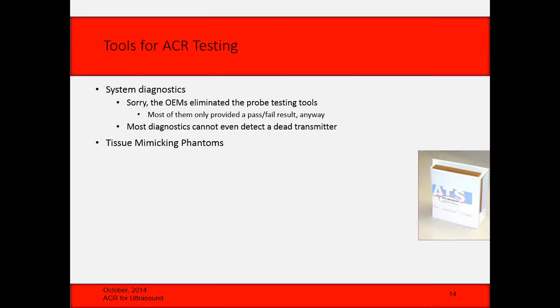You have to have a Doppler phantom, an elevational beam width phantom, you have to have a high-frequency linear array axial resolution phantom, and on and on. And it would take you a couple of days, by the way, to do your PM if you did that. It takes about 4 hours to set up the stupid Doppler phantom. And the good thing about phantoms, by the way, is they've been around and people know what they are, and most of us have one.